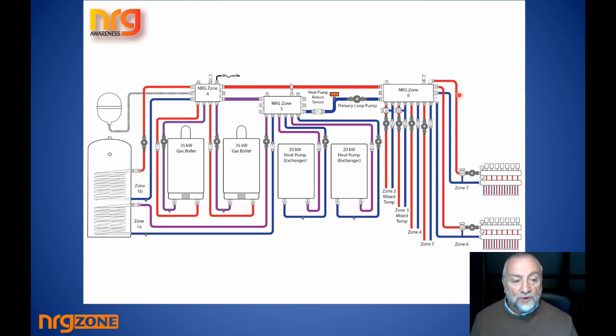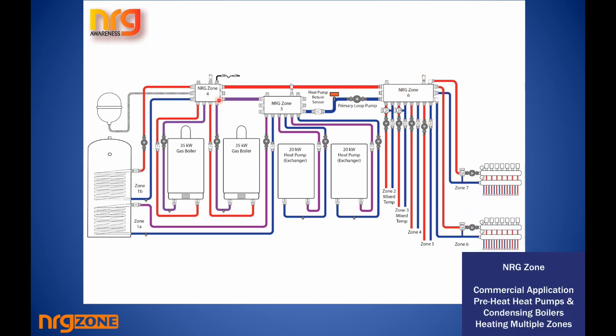But if I now want to heat this manifold, we've got a NRG 4 because we're heating just two gas boilers. We're using the side connection, NRG 5, because we're using one of each side connection, and we have a circuit going to the low temperature cylinder, and then we have the two heat pumps. And then NRG 6 because we want to have a mixed temperature circuit, a second mixed temperature circuit, two full temperature circuits, and two underfloor circuits. Now we've got 6 zones off this manifold.